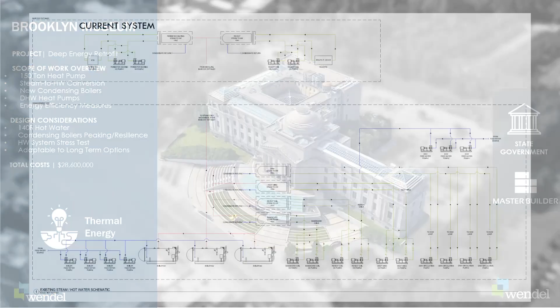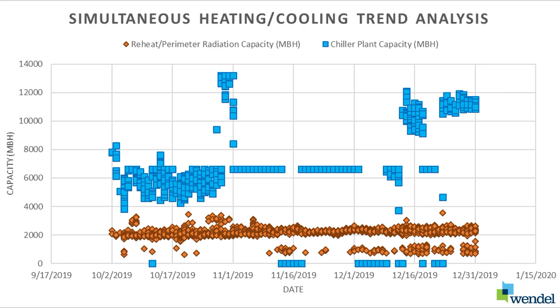We monitored the building from the BMS and quickly determined there was an opportunity for simultaneous heating and cooling, which was the centerpiece of our conversion. We took advantage of the high COP from the heat recovery, and were able to essentially handle about 35% of the building loads in terms of heating and cooling. We packaged that with a bunch of other ECMs or EEMs, energy efficiency measures, to enhance the life cycle cost.